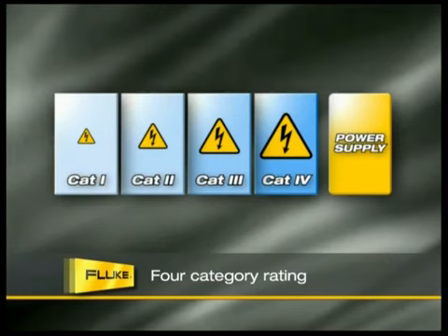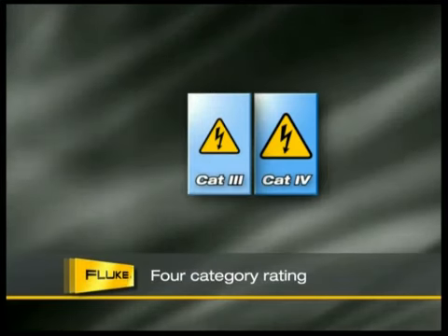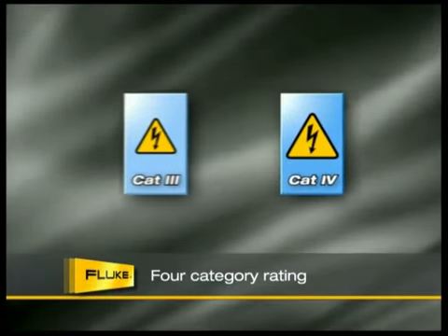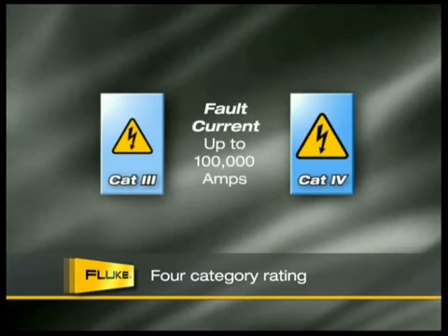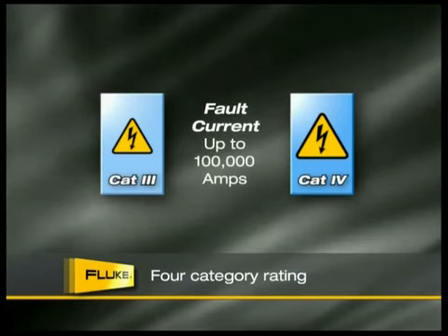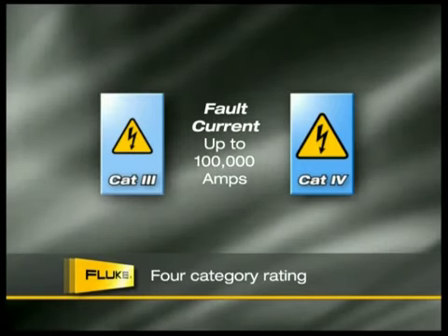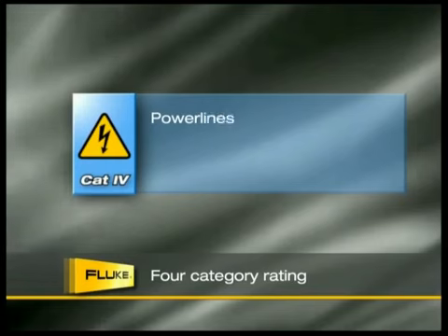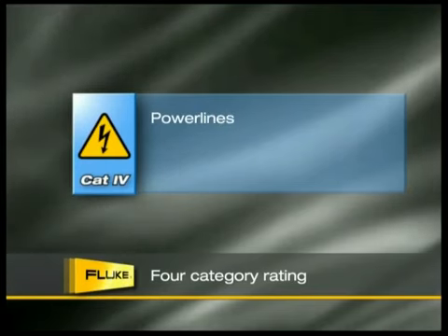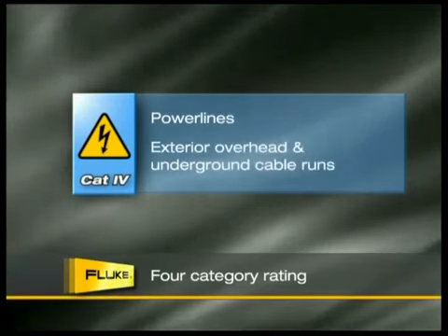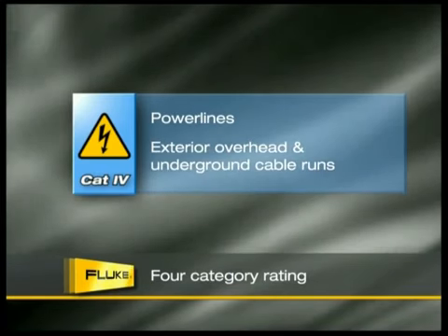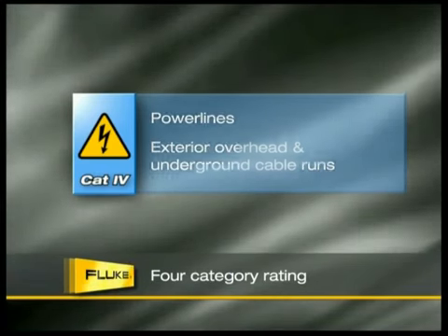In the 4-category rating system, the closer you are to the power source, the higher the category, and the greater the danger. Transients in categories, or CATs, 3 and 4 can be extremely dangerous. The available fault current in these high-energy circuits can reach as much as 100,000 amps. Cat 4 refers to power lines at the utility connection, but it also includes exterior overhead and underground cable runs, since both may be affected by lightning.